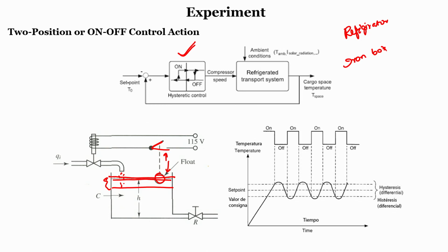To understand the system even better, if I say this is my set point, consider this is 50 degrees. In case of hysteresis or an on off controller, you will always have to set two thresholds. So, let us say this is 55 and this is 45. If your input temperature keeps on increasing more than 55 degrees centigrade, this is your higher threshold point, and this is your lower threshold point.